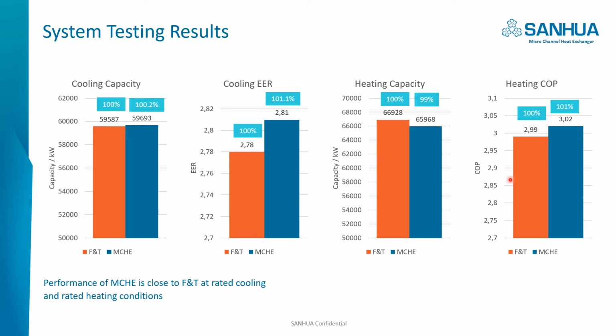The right two charts are about the heating performance. Microchannel capacity is 99% of the fin tube, and the heating COP is 1% higher. So generally, microchannel is very close to the fin tube at the rated cooling and heating conditions.